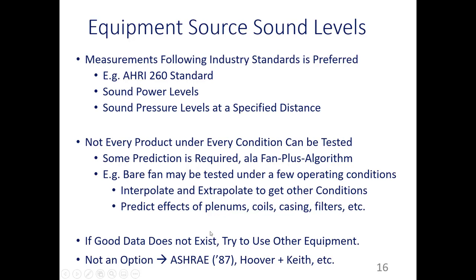So then if good data does not exist, try to use other equipment. And finally, if that's not an option, then use some predictive method like ASHRAE 87. I also have Hoover and Keith here. That's a good reference. This ASHRAE 87 one was just for fans. But Hoover and Keith, they publish a lot of things for chillers, package rooftop units, pumps, all the equipment that a mechanical engineer might be specifying. They at least give some method of getting in the ballpark.